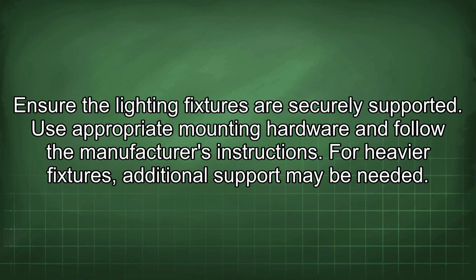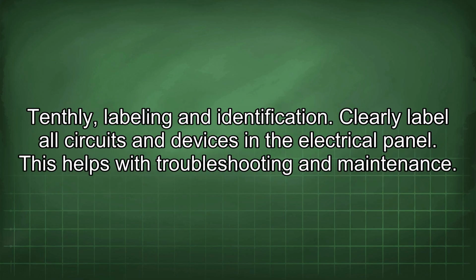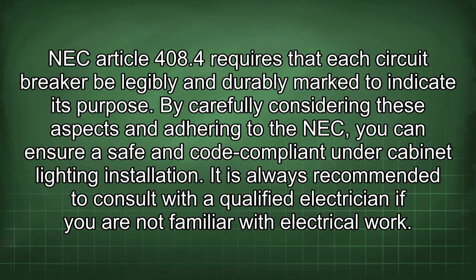For heavier fixtures, additional support may be needed. Tenthly, labeling and identification. Clearly label all circuits and devices in the electrical panel. This helps with troubleshooting and maintenance. NEC Article 408.4 requires that each circuit breaker be legibly and durably marked to indicate its purpose.